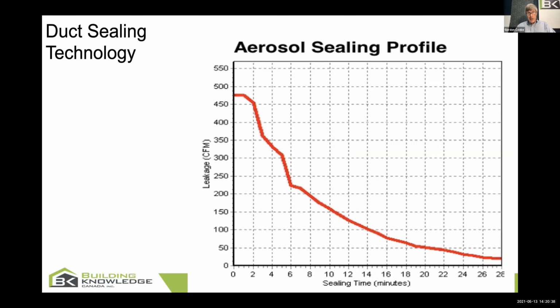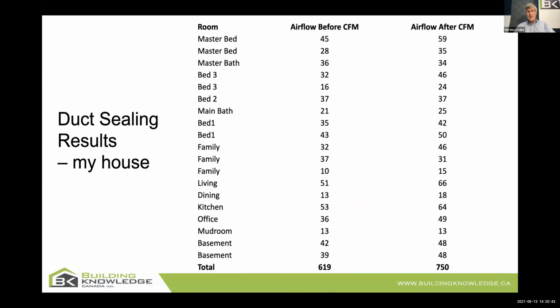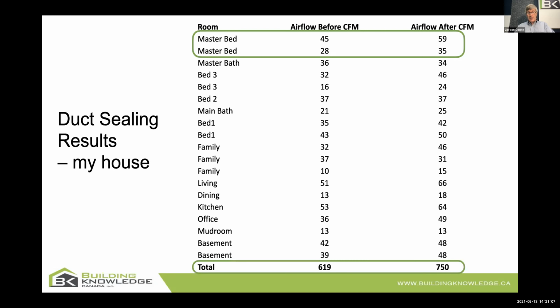And I'm going to say the room over the garage would really love this. Houses become much easier to control when you do duct sealing. Look at this room. The airflow before and after duct sealing went up by roughly 20%. So this happens to be my own house, the master bedroom. Just by duct sealing, I was able to get better flow to the end runs. So I'm just going to encourage you, the room over the garage becomes much easier to do if my ducts are sealed. Put that on your list of things to investigate. Notice the total airflow that actually got to the rooms I actually wanted went up by around 25% as well. In other words, I had 20% duct leakage, so pretty powerful.